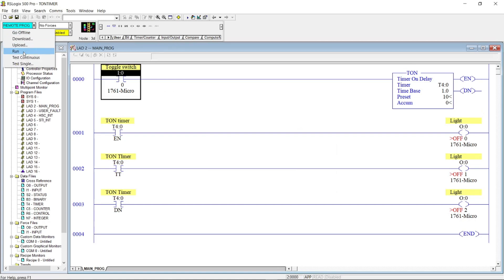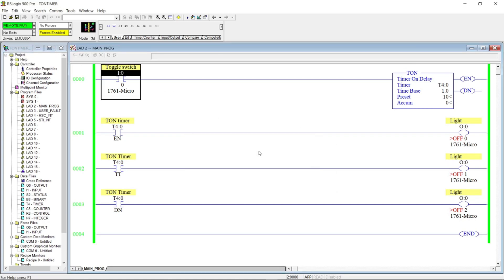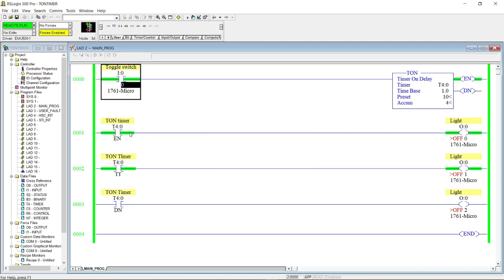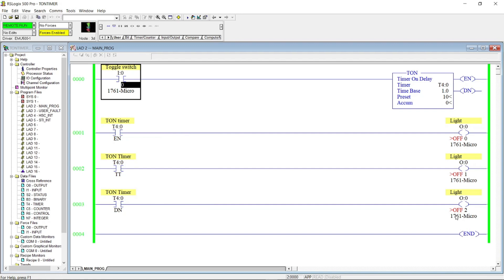Let's download the program and run it in simulation. Now let's energize the toggle switch. As you can see, the accumulated value is counting. When it reaches 10 seconds, the done bit timer will energize. When we de-energize the toggle switch, the accumulated value will reset to zero. This timer means delay turning on — after the input turns on, we wait 10 seconds before activating an output. This is the most common timer used in a PLC program.